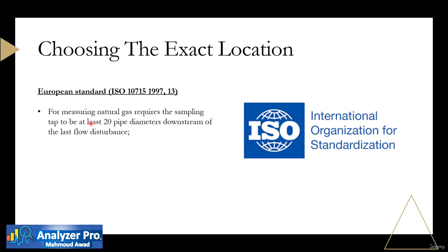The European standard for measuring natural gas requires the sampling tap to be at least 20 pipe diameters downstream of the last flow disturbance.